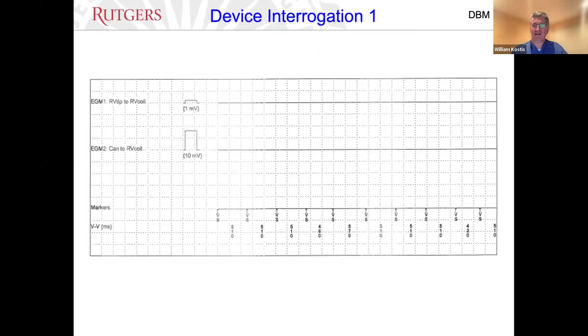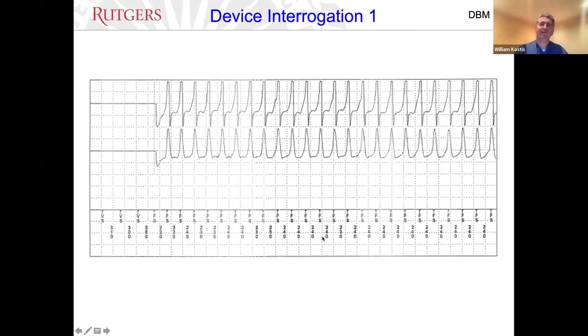So here's some tracings from a device interrogation. Here's the patient in a relatively normal rhythm. Well, they're a little fast, about 120 beats a minute. Here we go. They have a tachycardia with a cycle length of 240 to 250 milliseconds. It is rapidly detected by the device, and 8 pulses of anti-tachycardia pacing take place here, and it successfully terminates the VT, resulting in a safe perfusing rhythm without a shock.